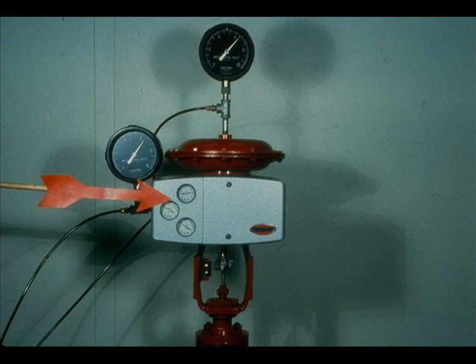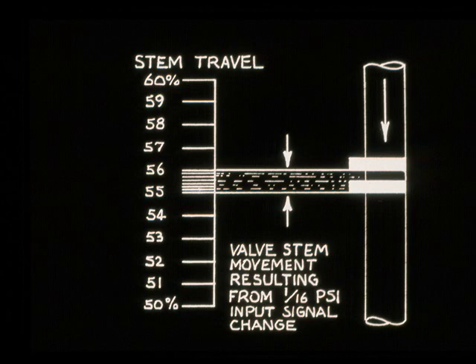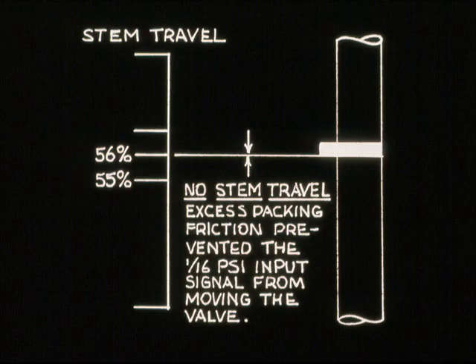The control valve positioner overcomes these factors and makes the valve stem move. Consider a control valve without a positioner that has an input change of one-sixteenth PSI. This one-sixteenth PSI is the only force available to move the valve stem. If there was no resistance, the valve stem would move the corresponding amount. But if the packing was too tight, the valve stem wouldn't respond.